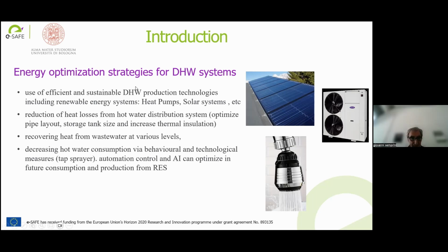Another aspect is the reduction of heat losses from the hot water distribution system by optimizing pipe distribution and increasing thermal insulation when possible. As I said before, in existing buildings this is quite complicated because the pipes are embedded in the wall, and only limited interventions are possible inside the thermal power plants. Another possibility is to recover the heat from wastewater at various levels, for example through a heat exchanger downstream of the hot water discharge. But these are only at the experimental stage at this moment.